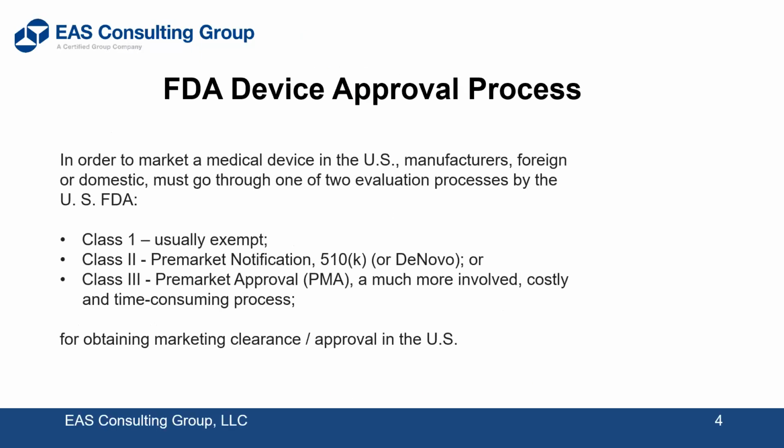First of all, we're going to look at the FDA's methodology for bringing products to market. Basically, if you have a class 1 device, the classifications are based on law, 21 CFR, the 800 series of law. You'll have to find your family of products there. If you can't, then your product is a class 3 and it's a PMA, and we'll talk about that. The classifications that the US uses is based on 21 CFR, Code of Federal Regulations, law. Classifications in Europe are based on the medical device regulation and annex, and the various rules in the annex dealing with risk. The FDA's classification is also dealing with risk, but they have predetermined that.